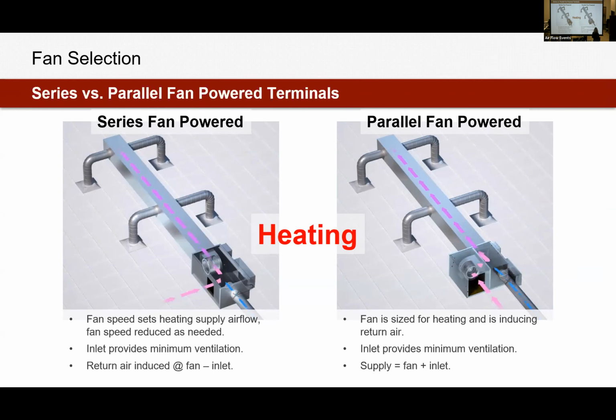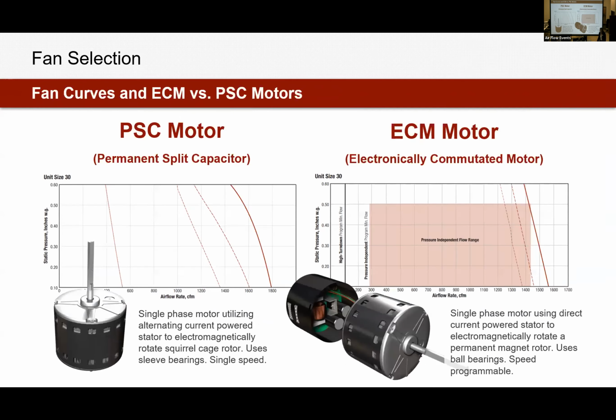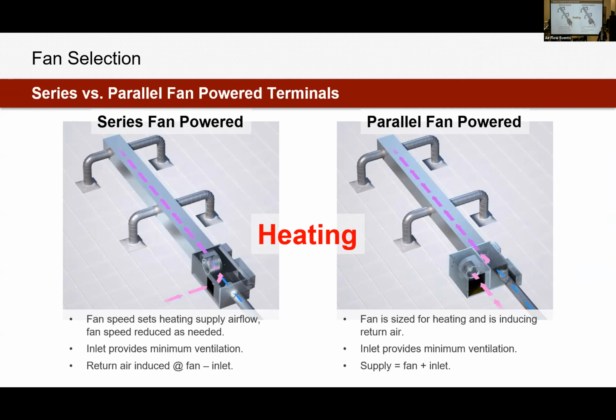The parallel box in heating, now we energize the fan. The fan is what's going to induce our air through the plenum, and these two streams are going to mix inside of the box before going downstream. Our fresh air is still turned down to a minimum, but our fan has to energize to draw anything else into the box. Any questions on series versus parallel, how they operate?